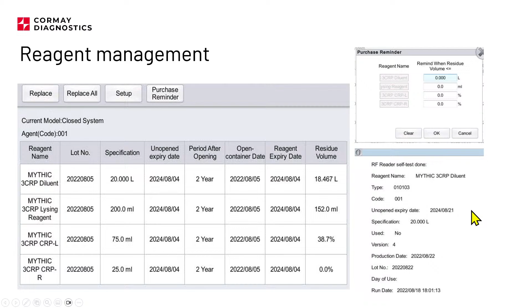Okay. What else can we see here? We have something like purchase reminders to the customer, or maybe not purchase reminders, but additional reminders that reagents will soon be empty. If you set those reminders, for example, if you set diluent to 5 liters, when the volume of the diluent reaches 5 liters, the customer will be reminded by the analyzer that the diluent is almost depleted. So this is some additional information. It can be useful, but it's up to you if you want to use it. If you set everything to 0, this will not be active.